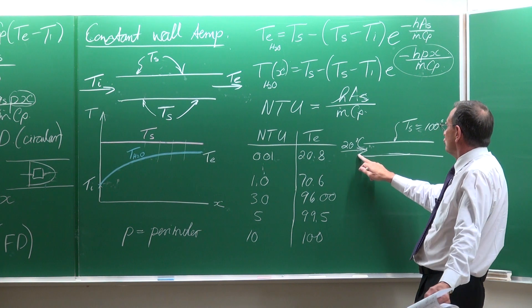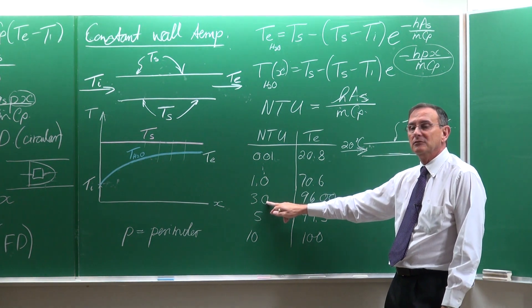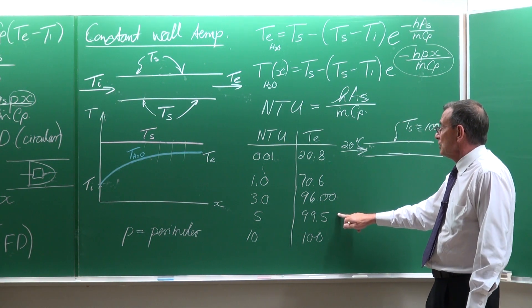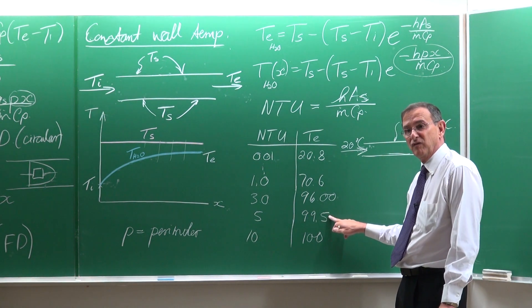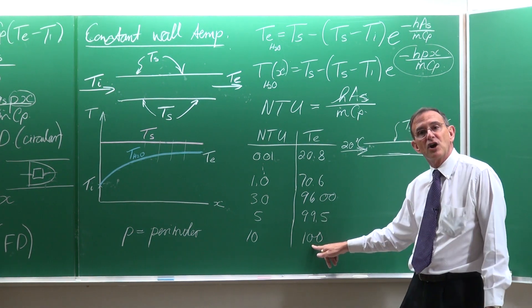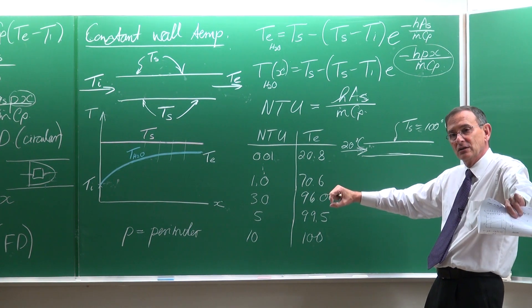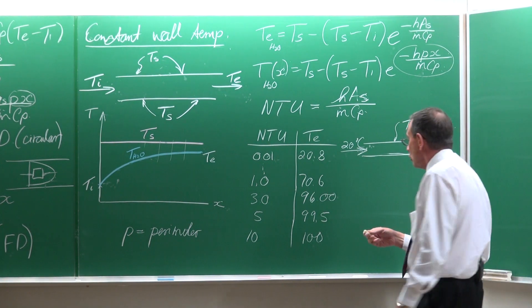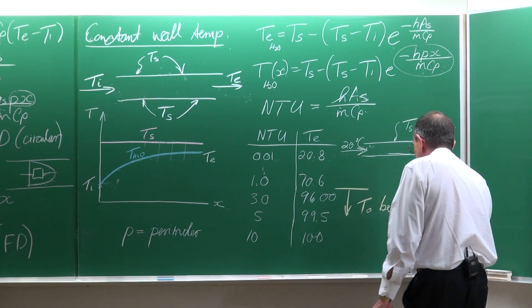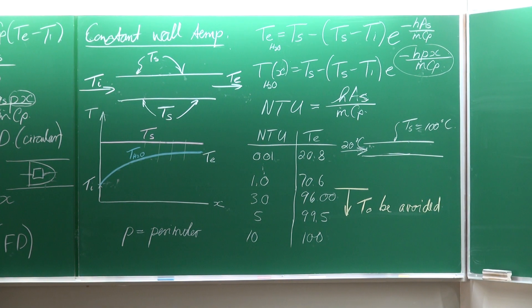What conclusion can you make from this? With water coming in at 20 and wall temperature at 100: if the NTUs are 3, you are within 4 degrees of the wall. If NTUs is 5, the temperature is 99.5 — almost the surface temperature. But from NTUs of 5 to 10, the temperature only increases 0.5 degrees, yet you've doubled the length of the heat exchanger. So as a rule of thumb, if you design a heat exchanger and the NTUs start becoming 3 and higher, then you start wasting material.